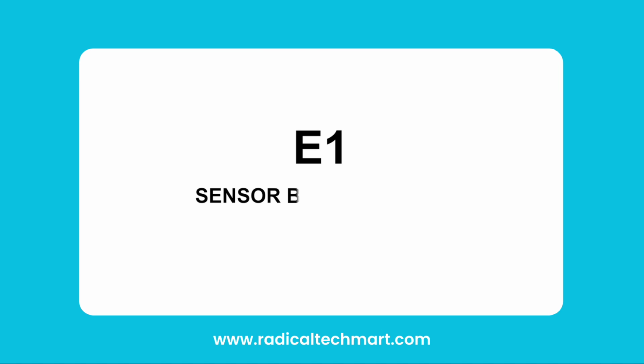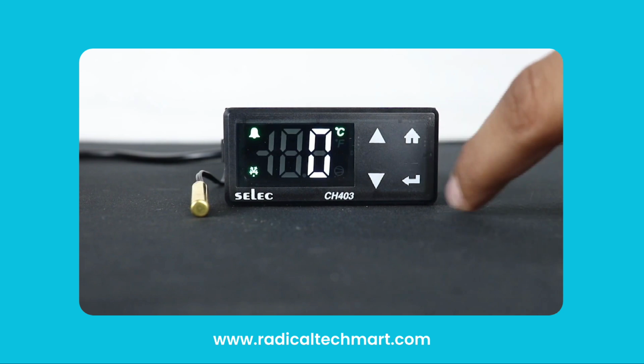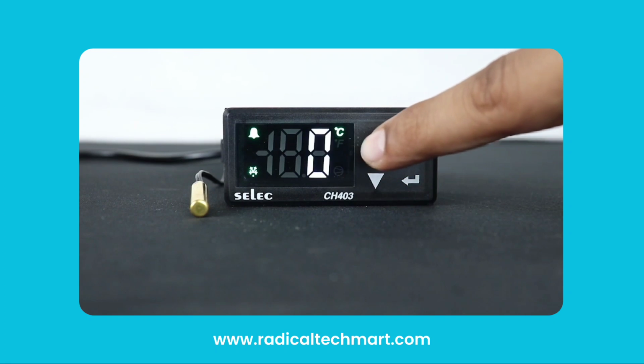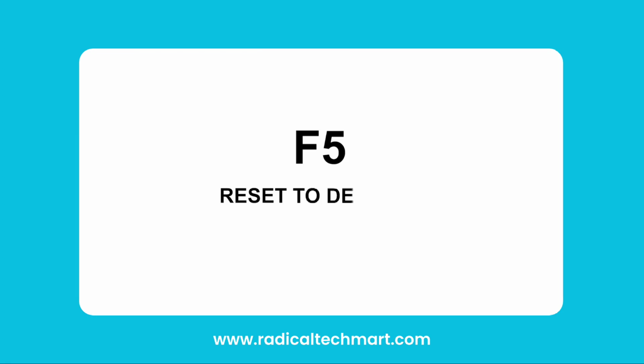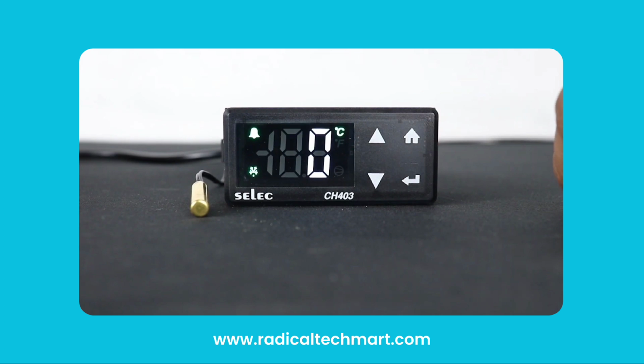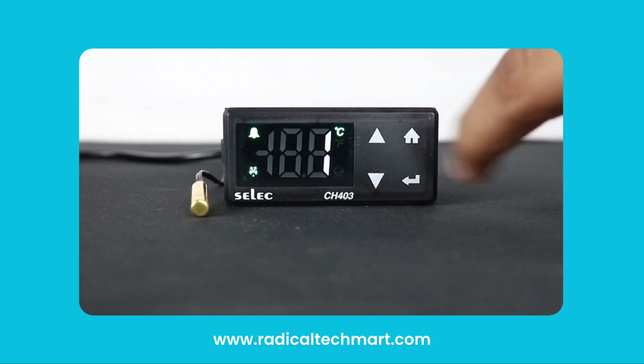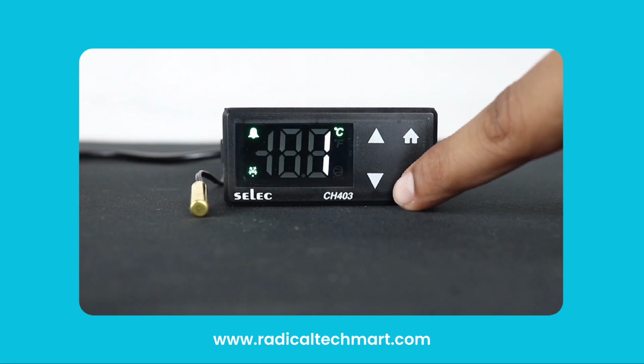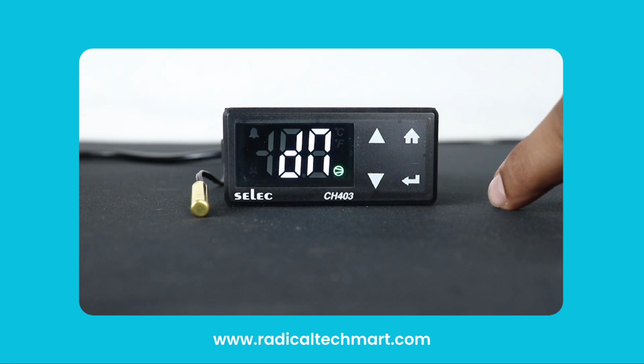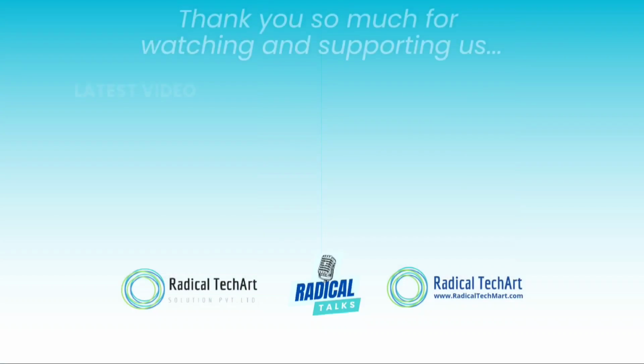Now, E1 means sensor break alarm. It provides an alarm on the display when any fault condition occurs because of the sensor. At last, we have F5, which implies factory default settings. After changing the value to 1, press the Enter key, and the display will show Done, and all the parameters will go back to the default setting. To exit the programming mode, press the Home key for 3 seconds.